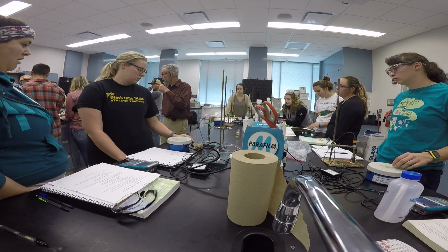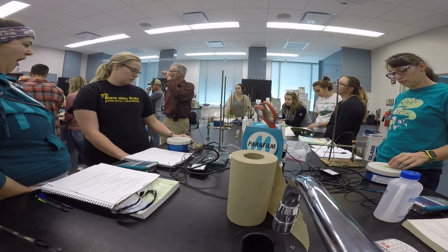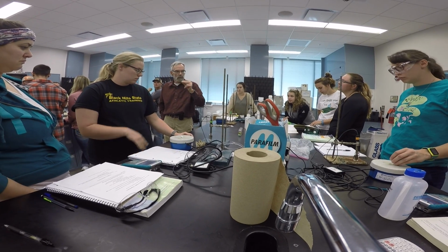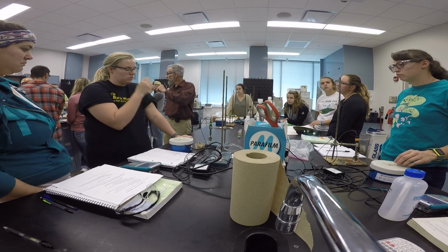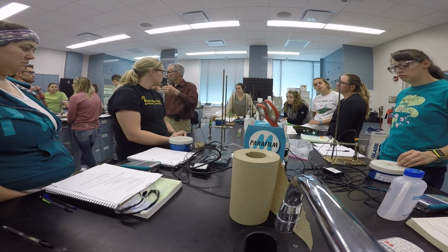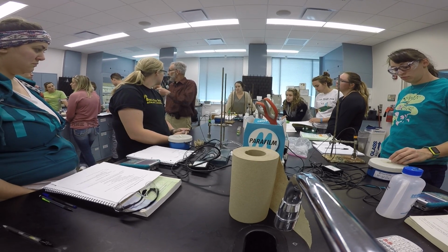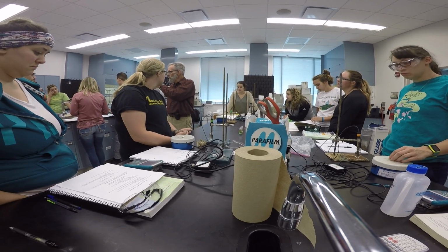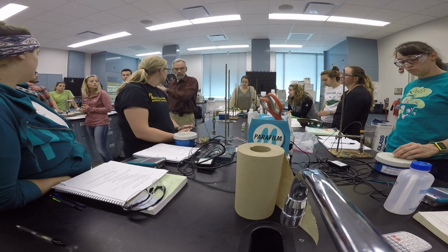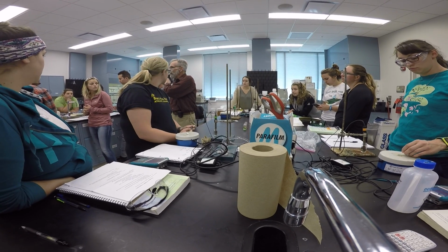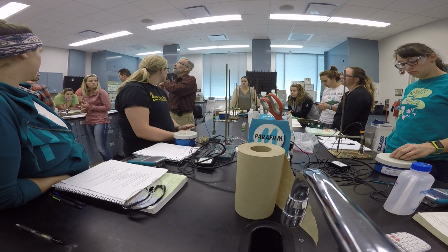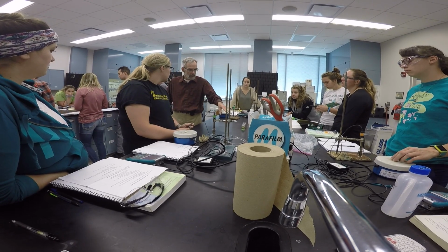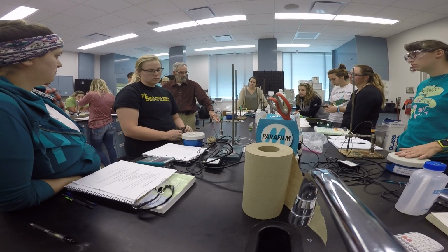And that does require, if I gave you one buffer at pH 7, or one buffer at pH 3 to make, and another buffer at pH 10 to calibrate, you have to redo the calibration between runs. And when you get to your unknowns over there, if your pH probe was calibrated between 7 and 10, but you grab an unknown over there that's a pH 3, you should recalibrate it before you measure that pH 3. So you always have to calibrate it as close to the proper pH as you can.